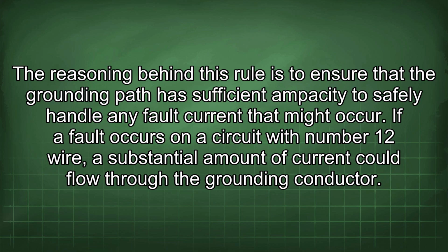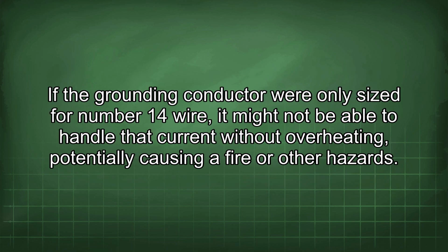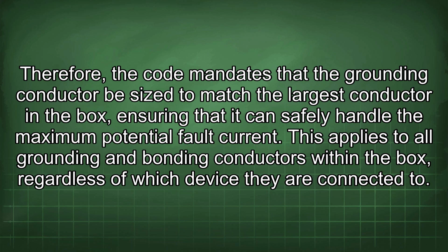If a fault occurs on a circuit with number 12 wire, a substantial amount of current could flow through the grounding conductor. If the grounding conductor were only sized for number 14 wire, it might not be able to handle that current without overheating, potentially causing a fire or other hazards. Therefore, the code mandates that the grounding conductor be sized to match the largest conductor in the box, ensuring that it can safely handle the maximum potential fault current.